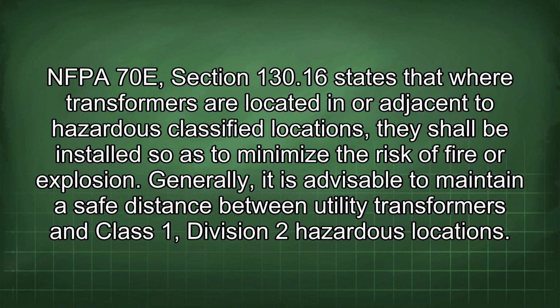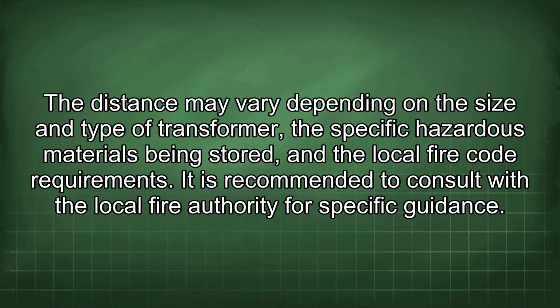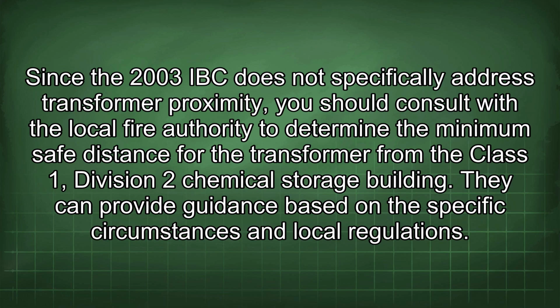Generally, it is advisable to maintain a safe distance between utility transformers and Class 1, Division 2 hazardous locations. The distance may vary depending on the size and type of transformer, the specific hazardous materials being stored, and the local fire code requirements. It is recommended to consult with the local fire authority for specific guidance. Since the 2003 IBC does not specifically address transformer proximity, you should consult with the local fire authority to determine the minimum safe distance for the transformer from the Class 1, Division 2 chemical storage building. They can provide guidance based on the specific circumstances and local regulations.